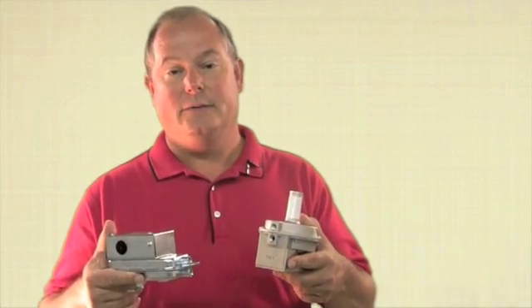If we have a small airflow and a small differential pressure, then we hook up two sensing lines differentially, one before the fan, one after the fan, and take a differential pressure measurement with this airflow switch.